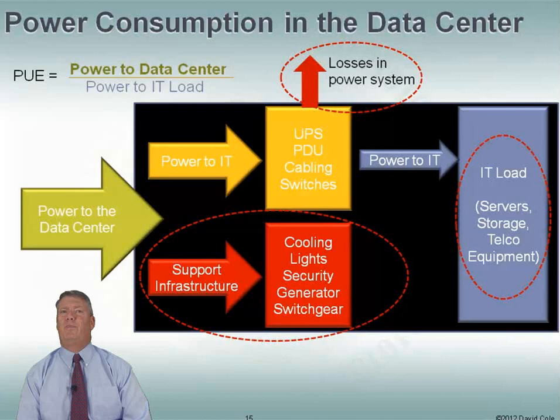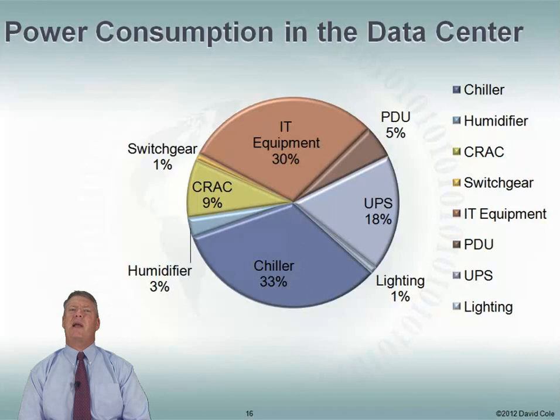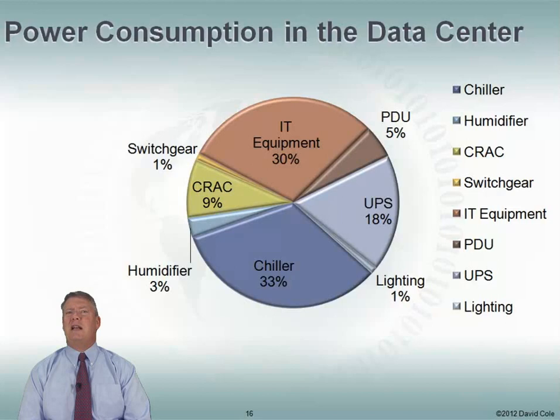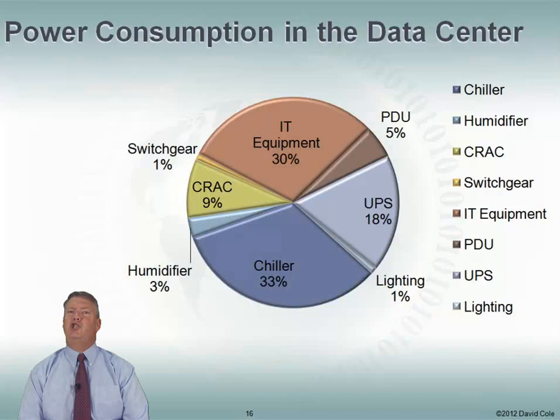Let's look at power consumption in the data center in more detail. Power going to IT equipment might be around 30%; the computer room air conditioner unit maybe 9%; humidifier, chiller, UPS, PDU, and lighting each take their share. The reason I break this up is that if I want to improve energy efficiency, I'm not going to start with lighting because that's only 1% of my total load. I want to look at the big areas: IT equipment, the CRAC unit, the chiller, and the UPS, because those are taking the bigger chunks.